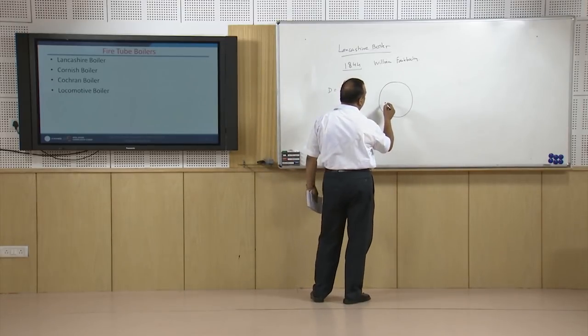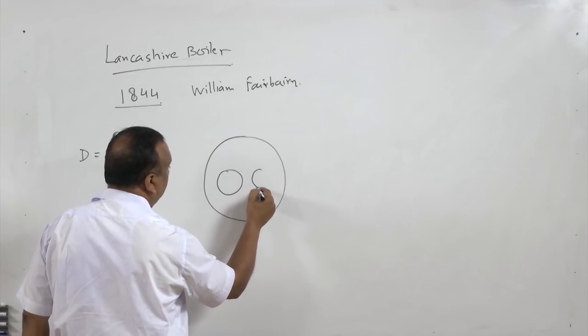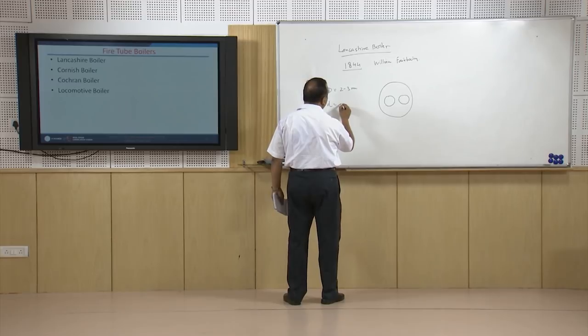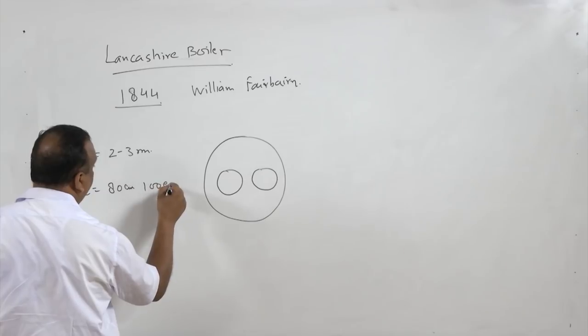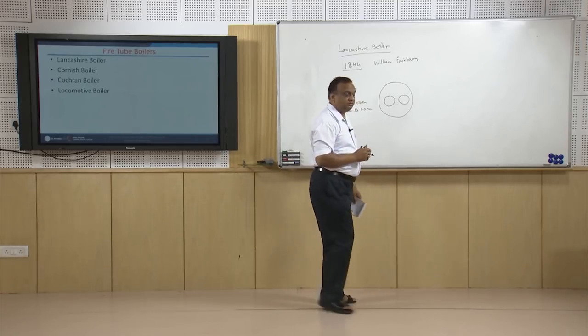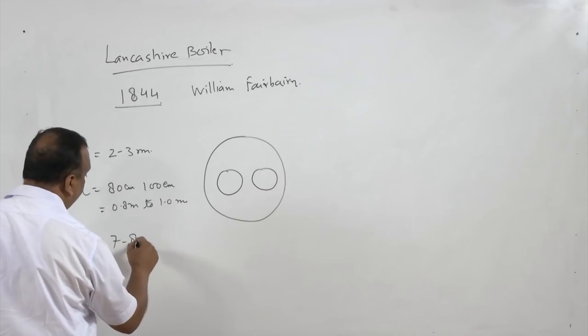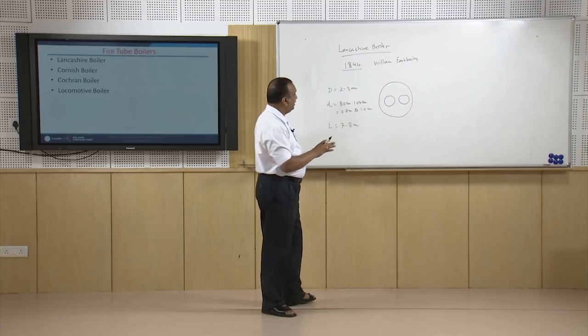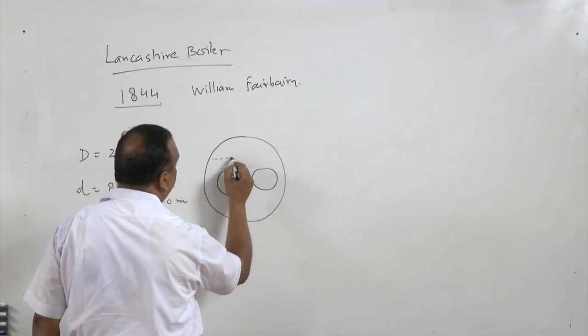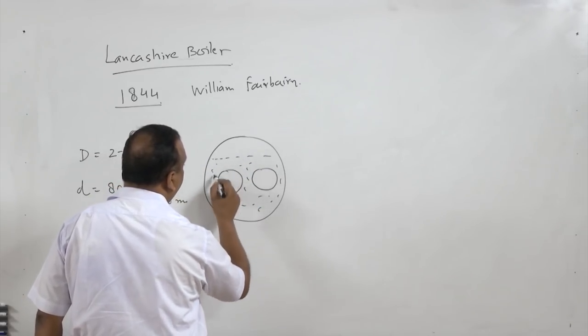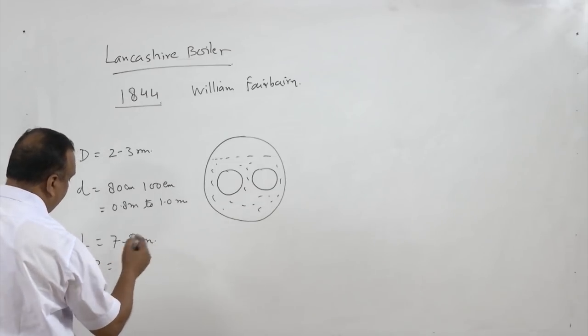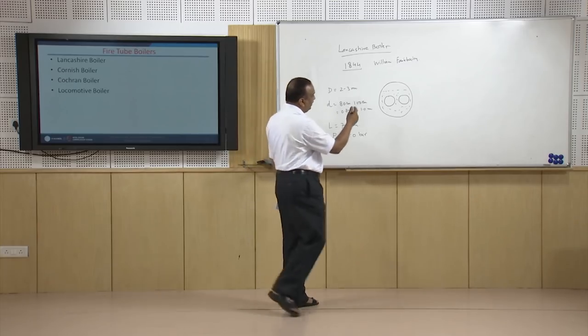Inside the shell there are 2 fire tubes of the same size, and the diameter of these fire tubes varies from 80 centimeters to 1.0 meter. The length of the cylinder is 7 to 8 meters. The flue gases after burning the fuel pass through these tubes. The shell is filled to a certain level with water and steam is stored at the top. The pressure of steam can go up to 20 bar in this boiler.